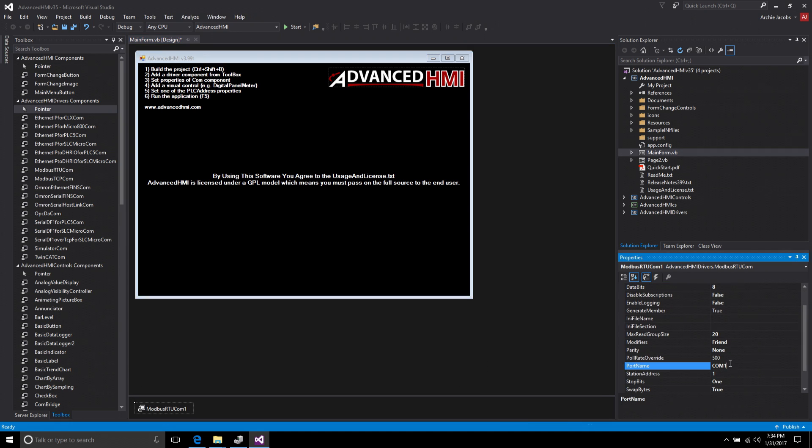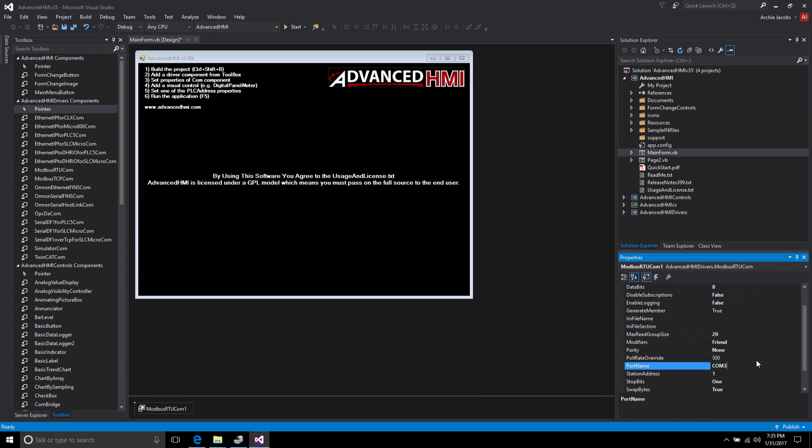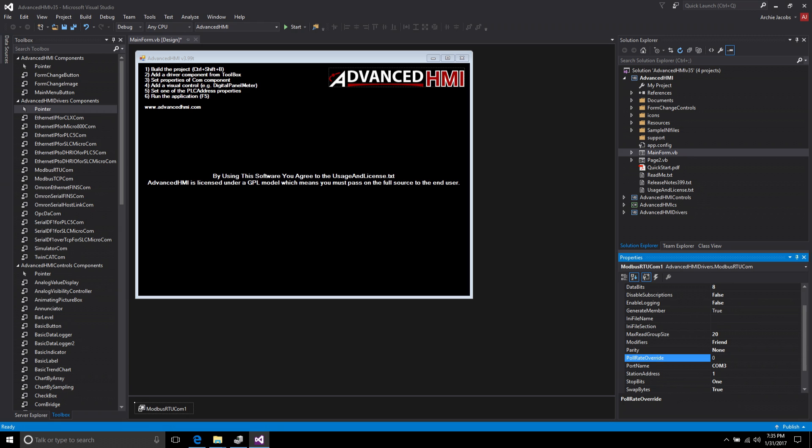Now the first thing I want to do is over on the port, the port name, remember we looked it up in Device Manager and discovered it was COM3. It's a USB mimicked COM port. All the other settings really aren't critical so we don't have to worry about the baud rate and so forth. But one other thing I do want to change in this driver is the poll rate override is at 500. That means every 500 milliseconds it's going to update. I like to really stress drivers and push things to the limit. So I'm going to change this down to a zero. A zero basically means let's read this as fast as we can and see how quick we can get data from this controller.